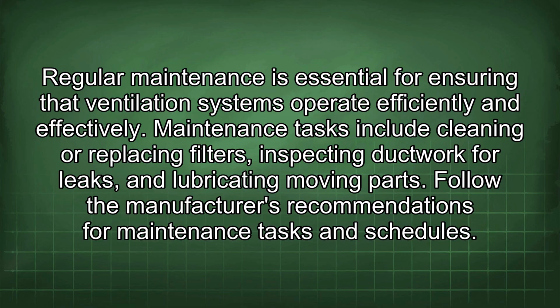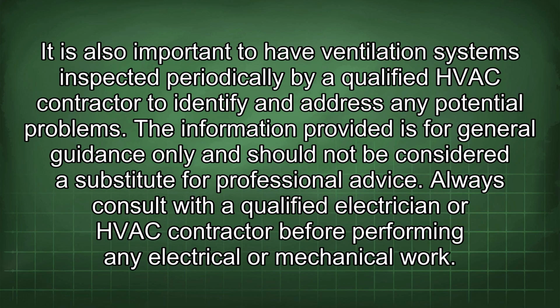Regular maintenance is essential for ensuring that ventilation systems operate efficiently and effectively. Maintenance tasks include cleaning or replacing filters, inspecting ductwork for leaks, and lubricating moving parts. Follow the manufacturer's recommendations for maintenance tasks and schedules. It is also important to have ventilation systems inspected periodically by a qualified HVAC contractor to identify and address any potential problems.